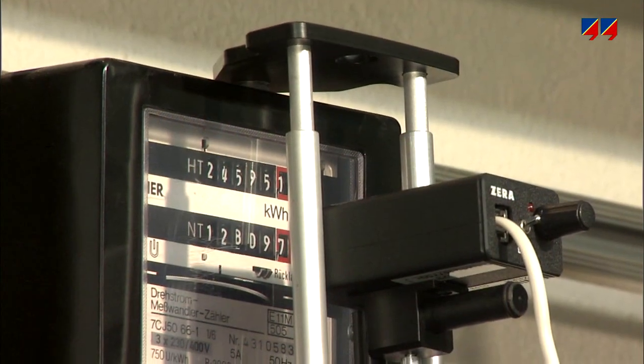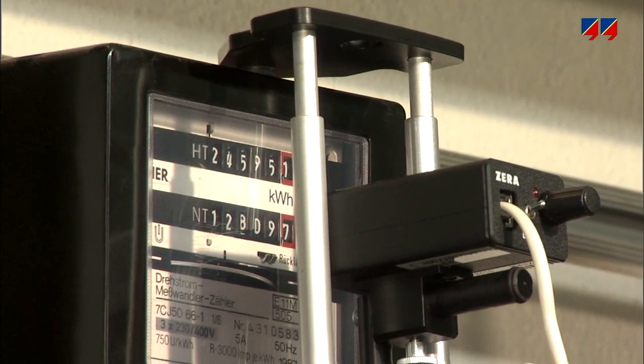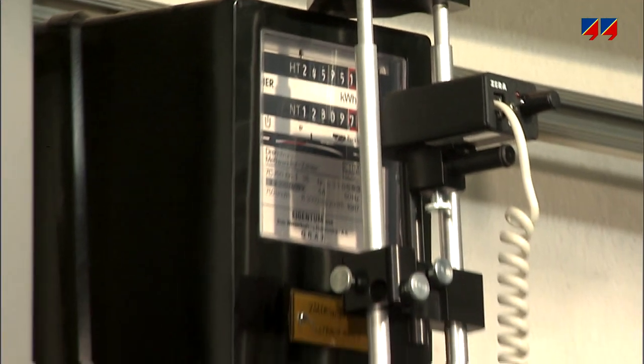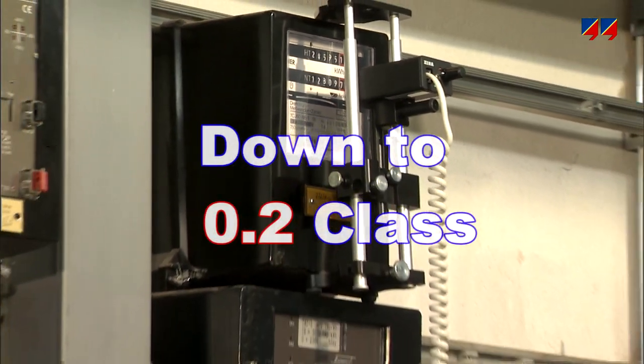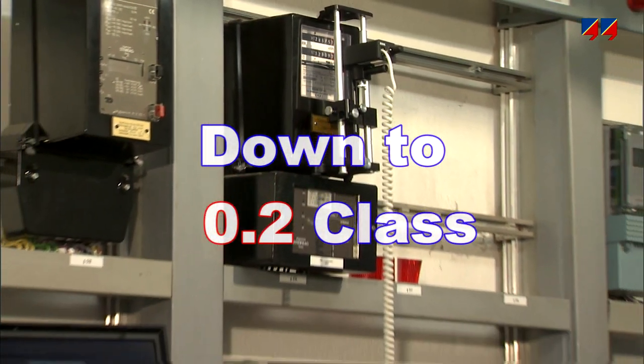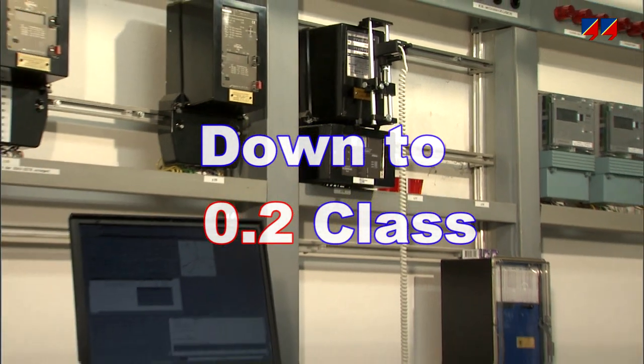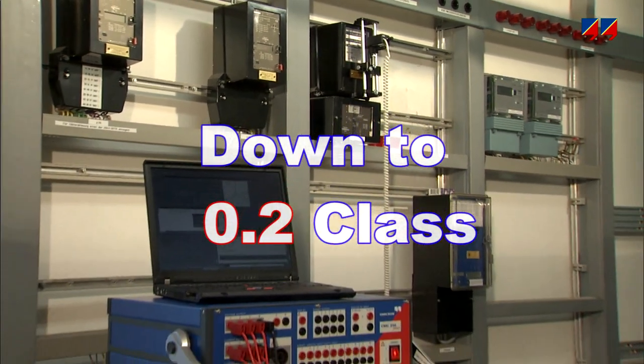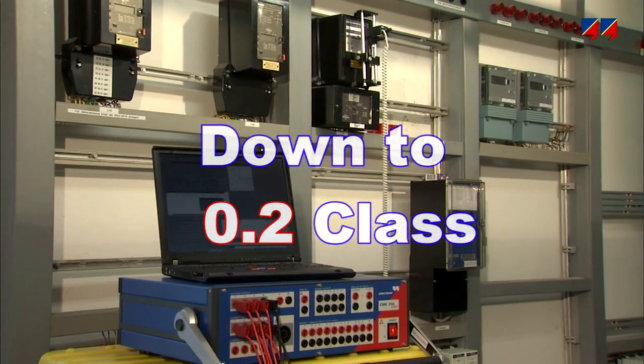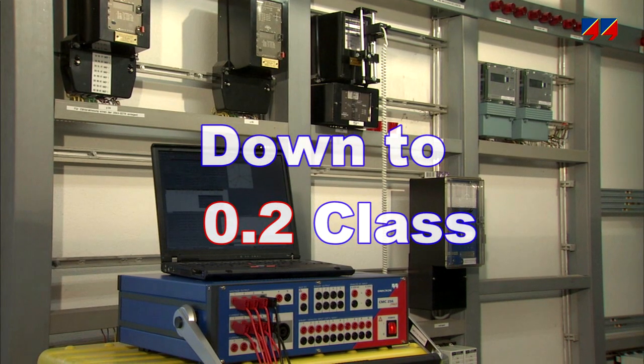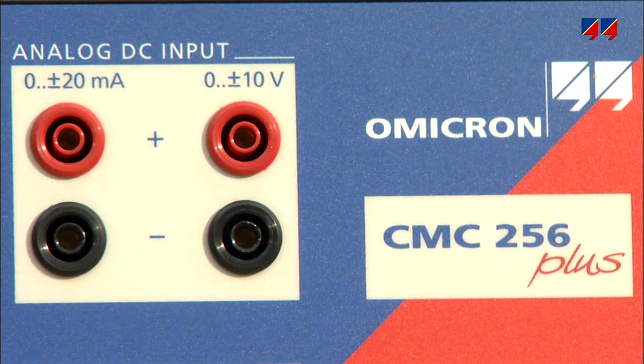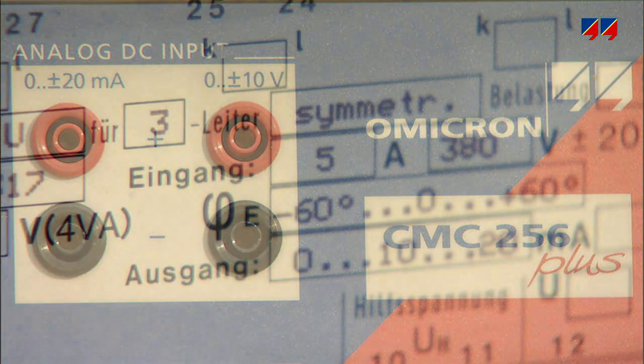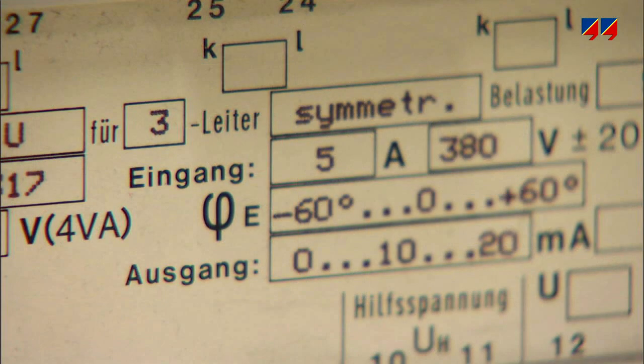The overall accuracy of the outputs of the CMC 256 Plus allows for comprehensive testing of energy meters down to 0.2 class. Here, the CMC 256 Plus signals can be directly used as a reference without the need of an additional reference meter. Using the 10 volt or 20 milliamp analog inputs, calibration of measurement transducers, again down to 0.2 class, is possible.